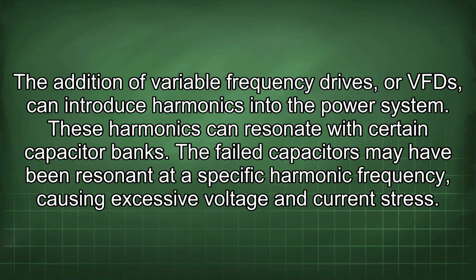The addition of variable frequency drives, or VFDs, can introduce harmonics into the power system. These harmonics can resonate with certain capacitor banks. The failed capacitors may have been resonant at a specific harmonic frequency, causing excessive voltage and current stress.